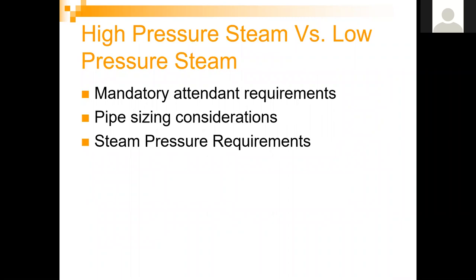Some considerations of high pressure versus low pressure steam: in California, high pressure has a mandatory attendant requirement, which is a big consideration. There are also pipe sizing considerations — low pressure steam has much larger pipe sizing requirements because you're sizing the pipe based on velocity, and steam is a compressible gas. Pipe sizing for low pressure steam is exponentially larger than for high pressure steam when transferring the same BTUs. There are also steam pressure and temperature requirements — if a process needs higher temperatures, you may need higher pressure steam.